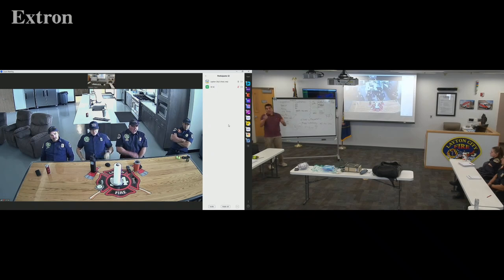If what you guys say is true, that it is PEEP compensating, that you put them on 10 over 5, and it's 10 over 5, if you increase this PEEP to 8, for reason of this tidal volume that is going to drop, you have to inherently then increase your IPAP the same amount that you increase your EPAP. Does that make sense? Are we clear on that?